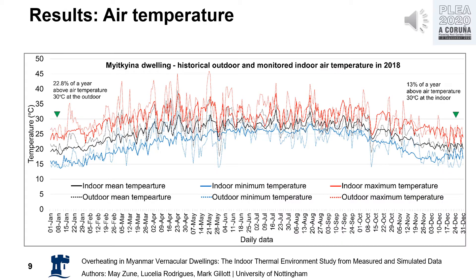In the comparison between year 2018 and the baseline typical weather year for outdoor conditions, we found the warmer hours above 30 degrees Celsius increased 1.8 times. In the outdoor weather, 22.8% of annual hours exceeded the dry-bulb temperature of 30 degrees Celsius. In the monitored dwelling, 13% of annual hours exceeded an air temperature of 30 degrees Celsius.